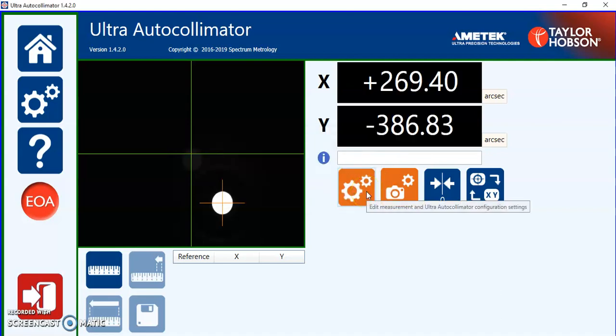Very important when you come into this software: if you see this warning it's telling you that the system is not calibrated. The calibration constants for the ultra autocollimator are stored on the PC not in the instrument, so it's important that the laptop has been propagated with those two factors for the X and Y correction. If those are filled in you will not see that error message again.